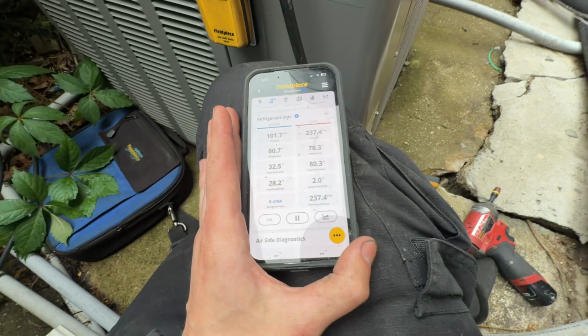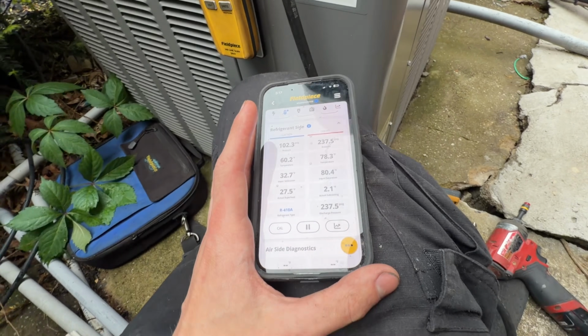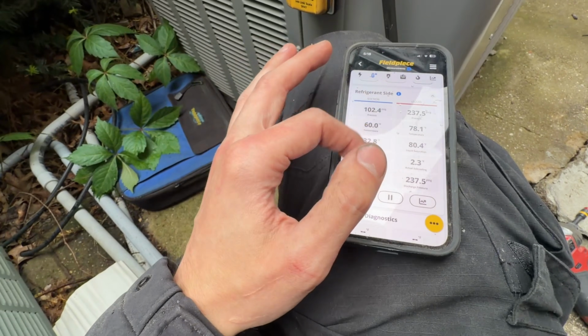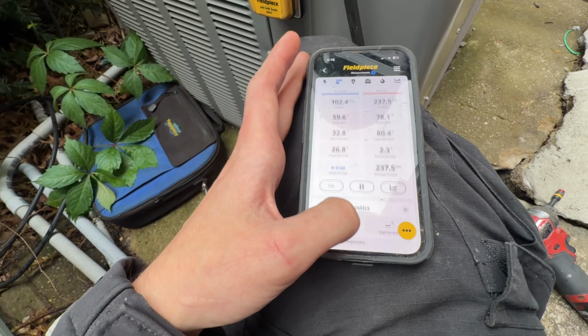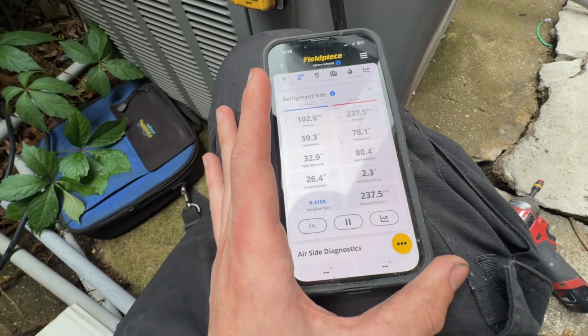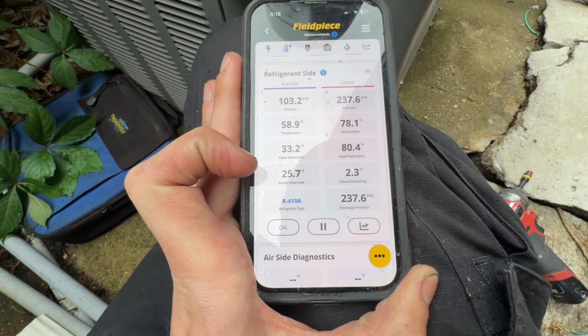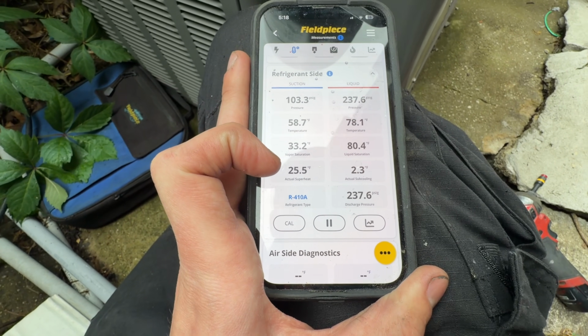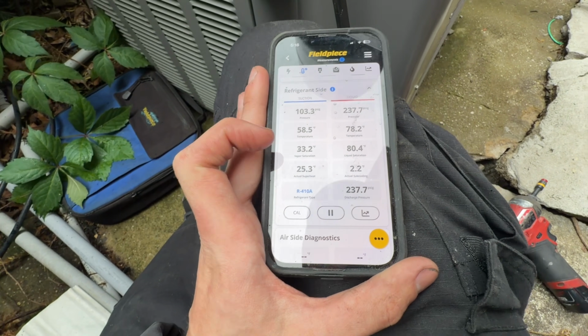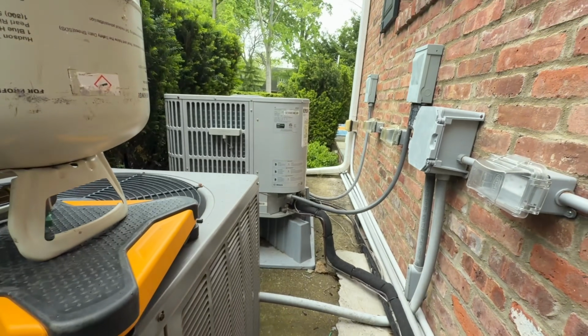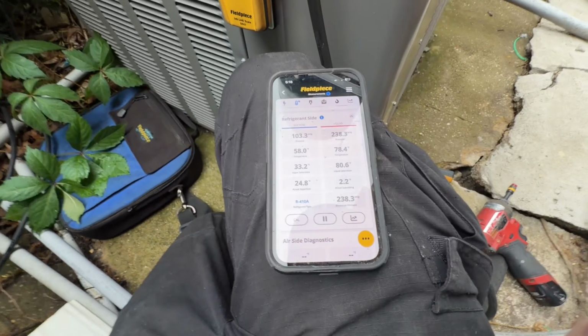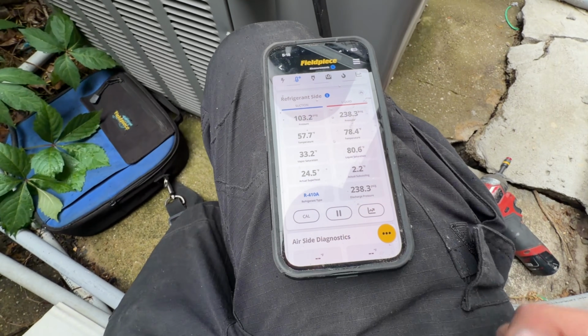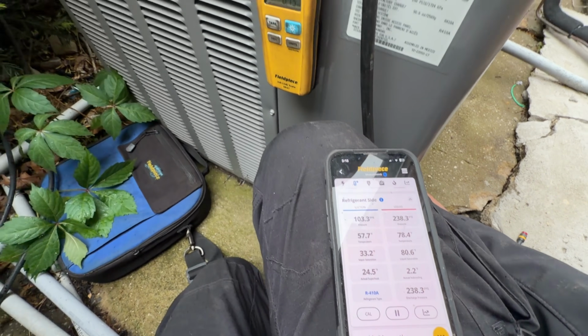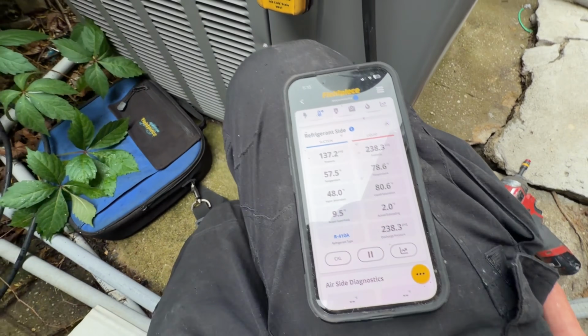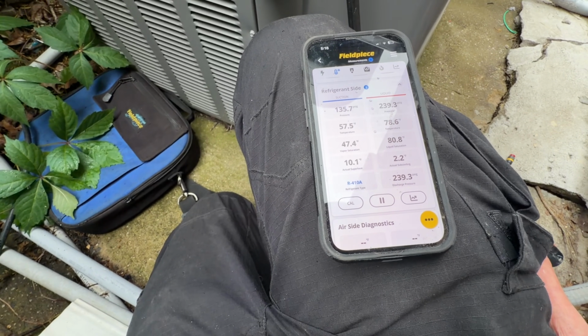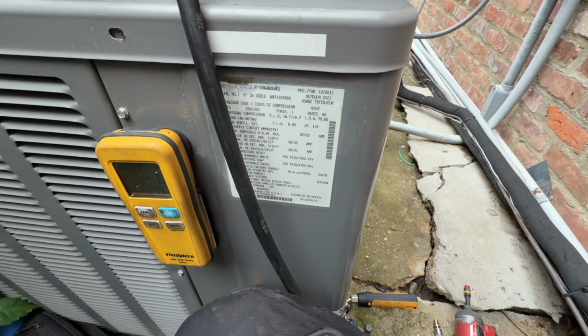And it's also a good idea, and I don't have it done right now, but you could take your supply and return temperature probes that link to your app, and you could put them in and see how that's doing. I'm not overly concerned at this particular job because I know that it has nice ductwork and is installed well. There's a Bosch unit that we installed in the attic right next to it. So I'm gonna go for a little bit more because I want to bring that subcooling up higher. Ideally 10 degrees of subcooling.